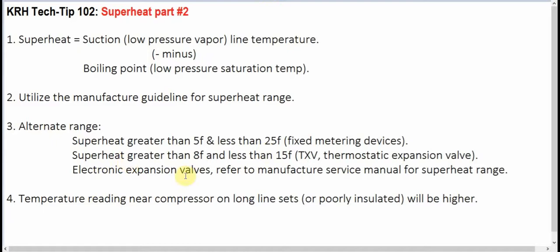For electronic expansion valves, refer to the manufacturer's service manual for the superheat range. To know what that is, you really will need to refer to the manufacturer's service tips or service tech information. The temperature reading that you're going to take, preferably you want to get as close to the evaporator as you can. However, that's not always convenient. You can't necessarily get to that and check your suction pressure as well to get your boiling point. So you will more than likely be checking it on split systems at the outdoor unit, and factor in or consider how long that line set is and is it well insulated.